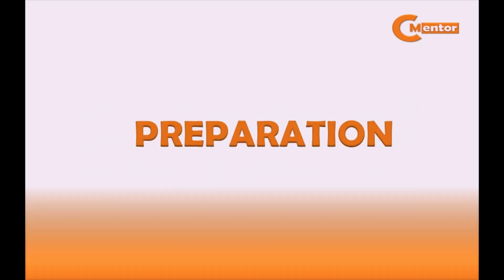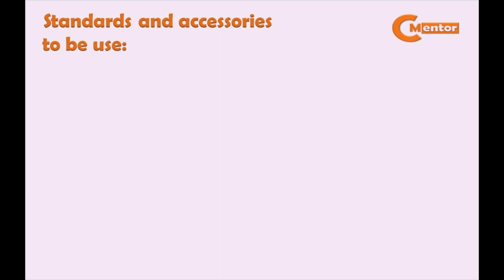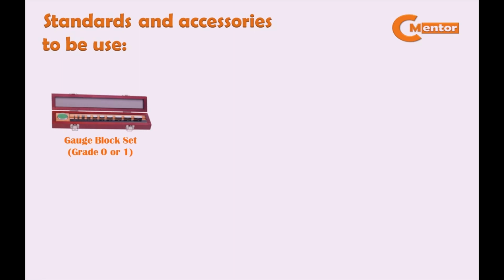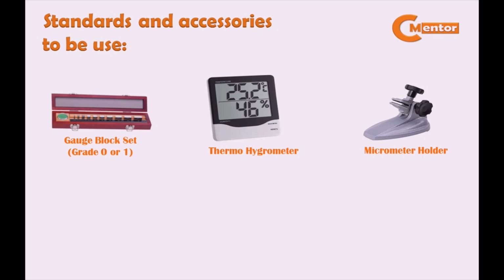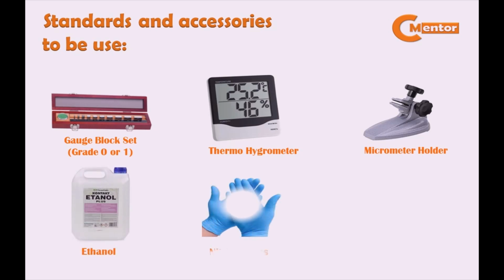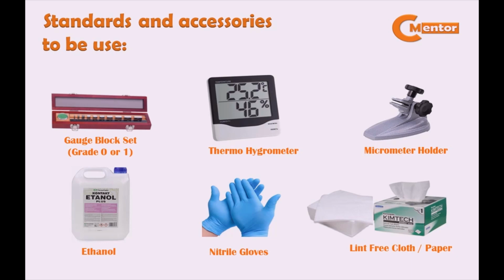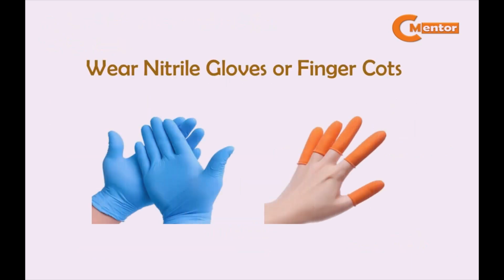First of all, we need to prepare our calibration standards, accessories, and cleaning materials. For standards and accessories to be used: gauge block set, grade 0 or 1, thermohygrometer, micrometer holder, ethanol, nitrile gloves, and lint-free cloth or paper. Take note to always wear gloves or finger cots before handling the micrometer. This is to ensure that the dirt, dust, oil, or other foreign particles from the micrometer will not be transferred to you or vice versa.